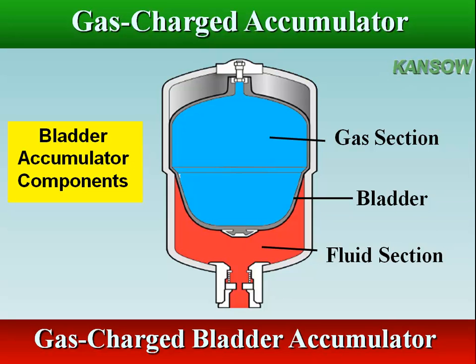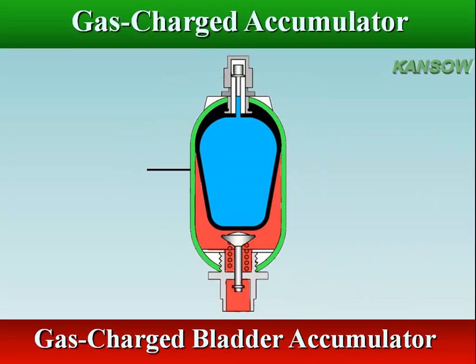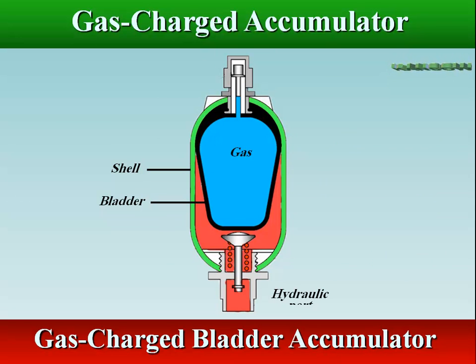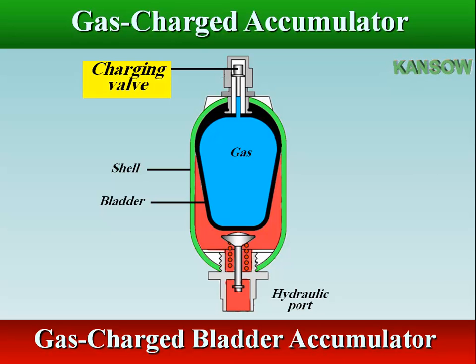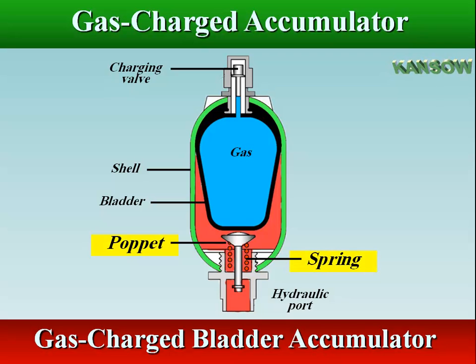The fluid around the bladder, hydraulic oil, is connected to the external hydraulic circuit. The accumulator is charged with nitrogen through a valve installed on the top. The accumulator will be pre-charged to nominal pressure when the pumps are not operating. A poppet valve, normally held open by spring pressure, prevents the bladder from extruding out of the fluid port.